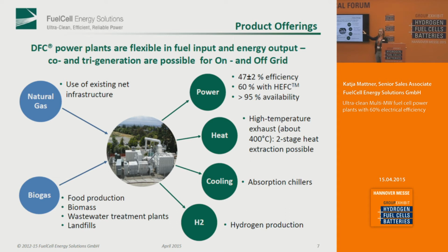We also have high temperature heat available, so the exhaust air from the fuel cell, which is actually air and not exhaust gas, has a temperature of roughly 400 degrees Celsius. So you can use it for steam applications, for standard heating, or for absorption chilling. If you drive those 400 degrees Celsius directly into an absorption chiller, you can use it for refrigeration or for cooling your buildings.